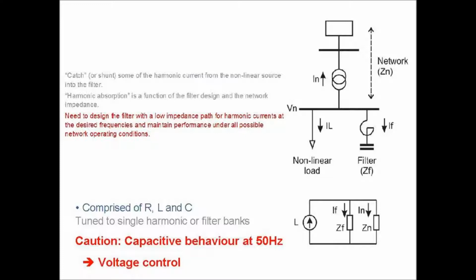I already mentioned that the impedance changes throughout the year from summer night valley all the way through to winter peak. So if you've got a passive filter that works great in summer night valley, it mightn't necessarily work at winter peak. So that's something to bear in mind when you're designing passive filters. As I said, it's RLC, and it's tuned to either a single harmonic or lots of harmonics, depending on how you want to do it, or you can have multiple banks of these filters all together.